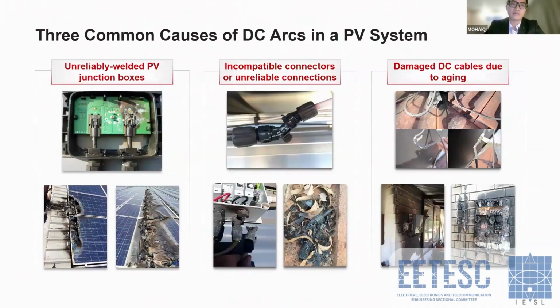Some unreliable PV junction boxes, which can happen with a central inverter or something similar, some incompatible connectors or unreliable connections, and damaged DC cables due to aging.